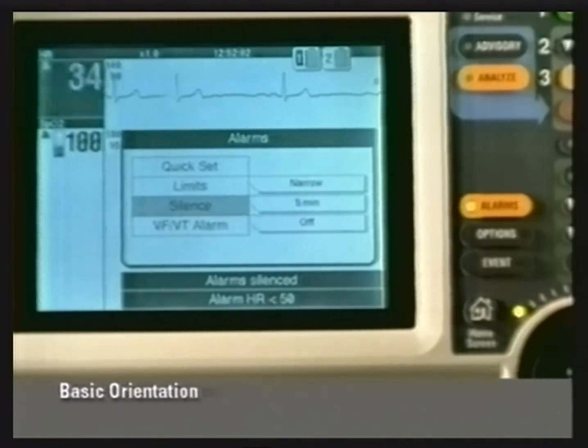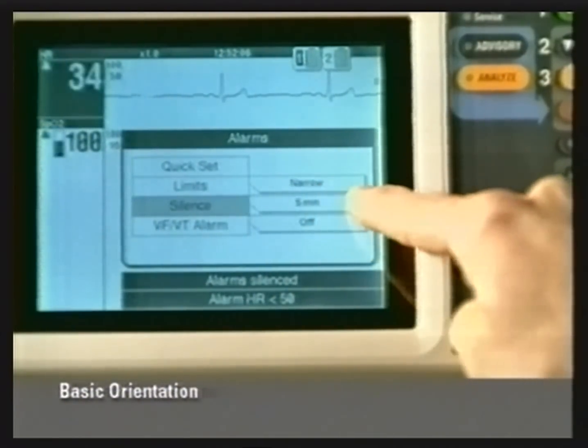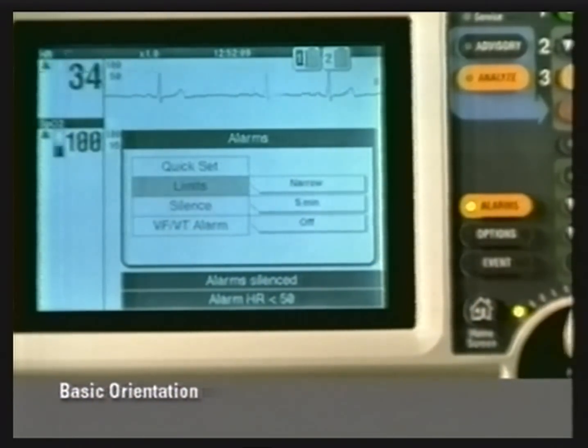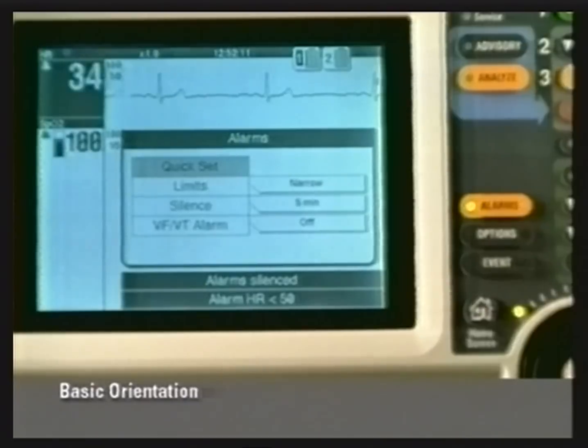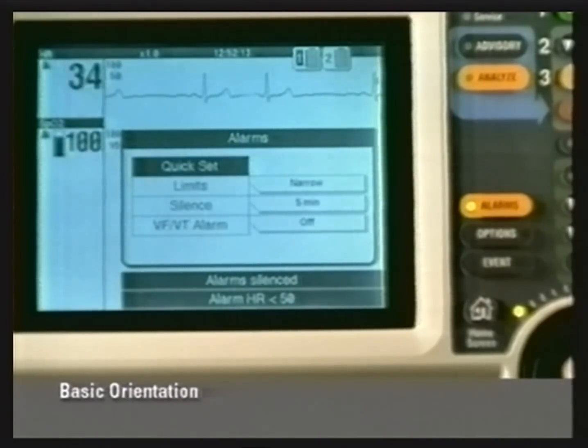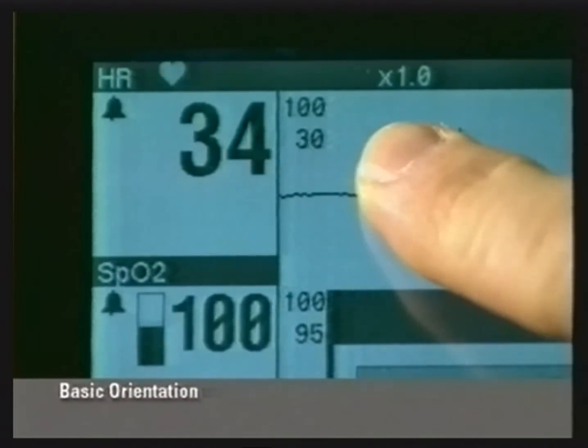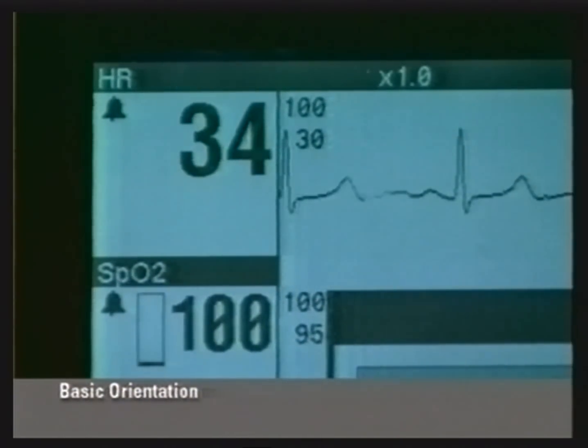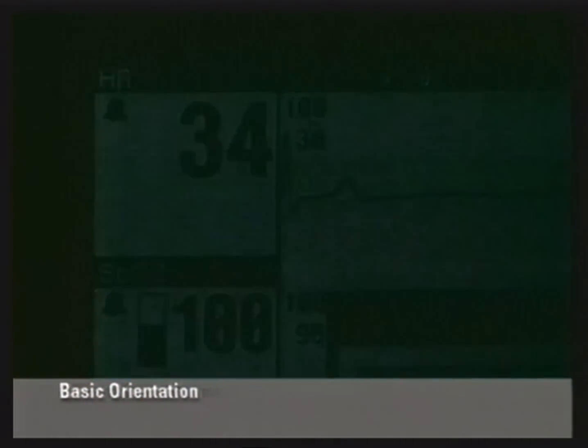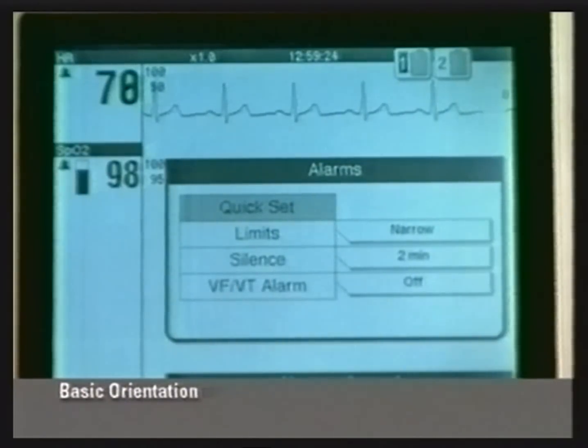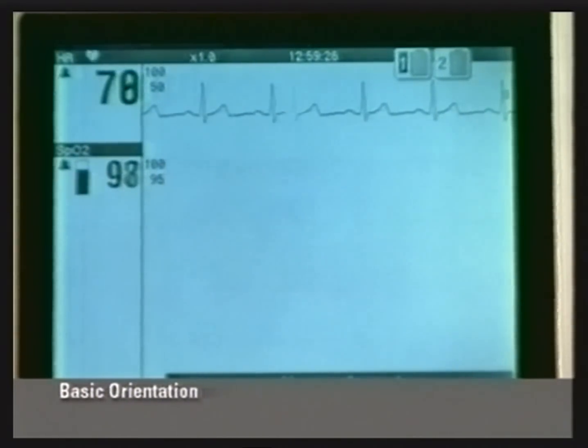Next, assess the cause of the alarm and whether narrow limits, if selected, should be set to wide. If the patient is unstable, do not reselect Quick-set. Reselecting Quick-set resets the limits around the patient's changed vital sign values. This may be outside the safe range for the patient. Only after the patient is stabilized should you reselect Quick-set if necessary.